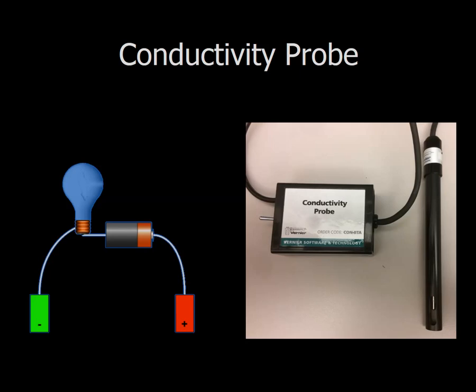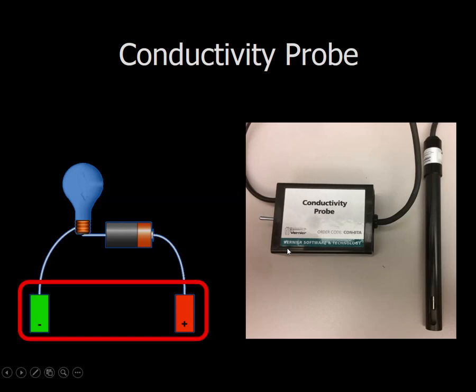So in lab, you're going to be measuring electrical conductivity using a probe. On the simulator we just looked at, there was a part that we submerged in solution. The conductivity probe you're going to work with is set up in a similar way. This part, this tip, gets submerged into the solution, and there's a hole in between that allows the solution to move back and forth.